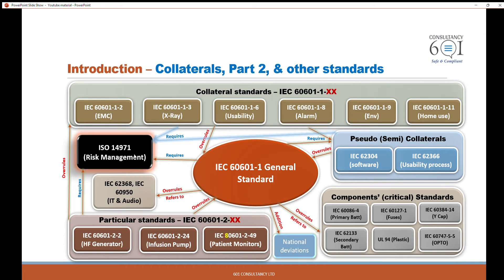When I say medical devices in this session, it means medical electrical equipment — this is important. In this session I'm going to discuss the standards to consider during the design and development, on top of the general standard which is IEC 60601-1, Medical Electrical Equipment Part 1, General Requirements for Basic Safety and Essential Performance, and also the relationship between the general standard and the other standards.